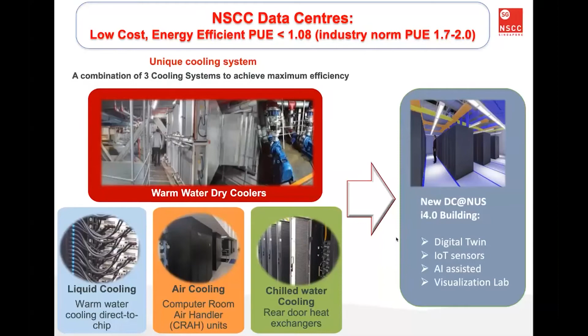We were able to use this warm water cooling system in our Aspire 1 facility to allow the temperature in the room to rise into the high 30s and even 40s, because our cold water inlet is actually at 40 degrees, and it heats to a water outlet temperature of 45 degrees.